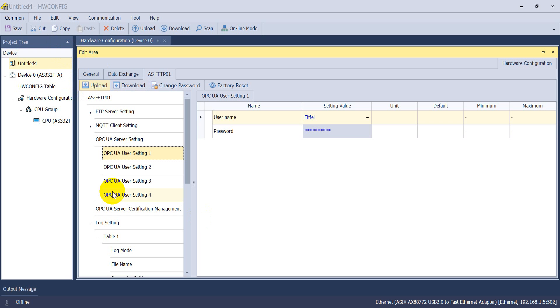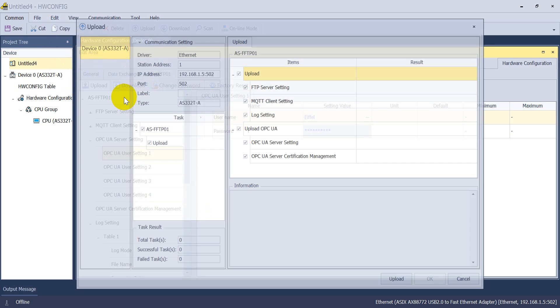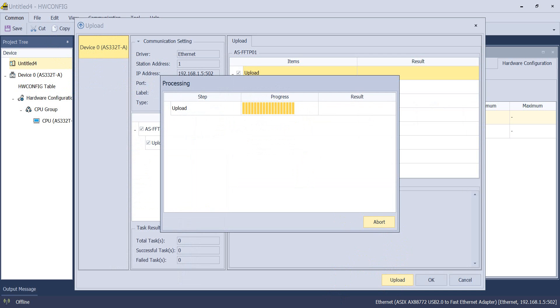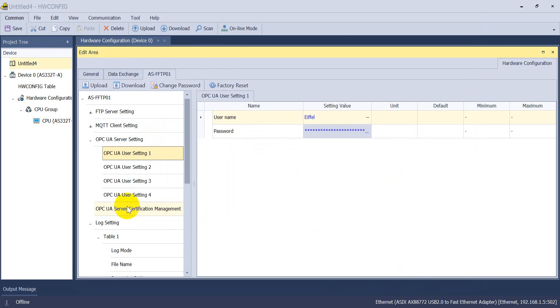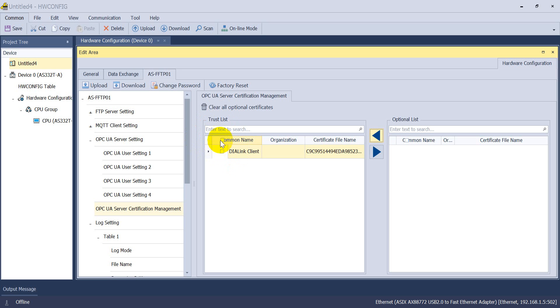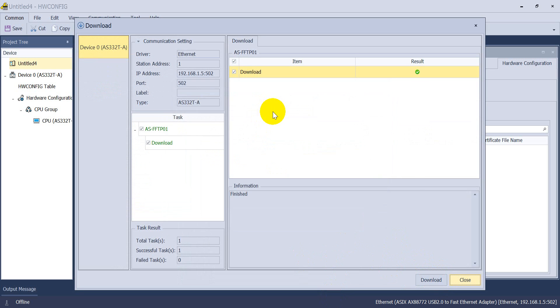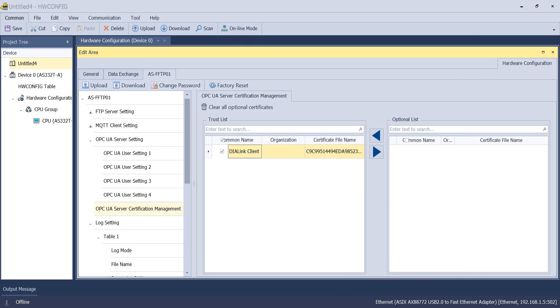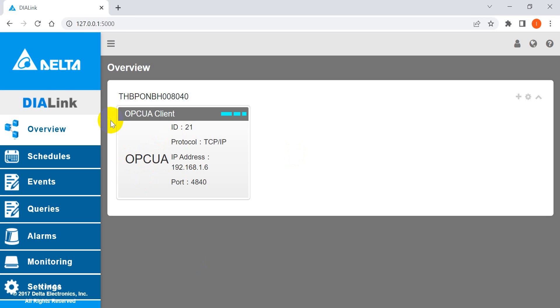Back in hardware config, click Upload from the AS-FFTP01 function card and click OK once done. Then go to OPC UA Server Certification Management, add the certificate to the trust list, and click Download to PLC. Once you download, the MS indicator will start blinking again — wait until it returns to normal, meaning continuous on.